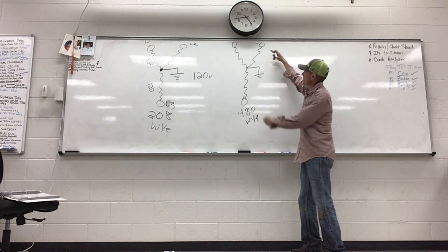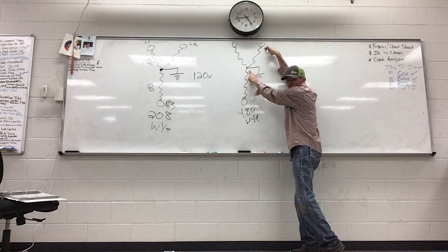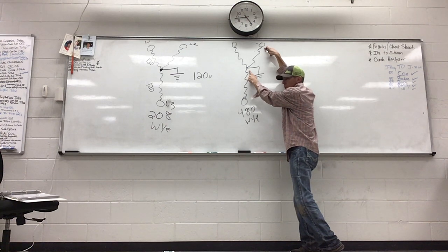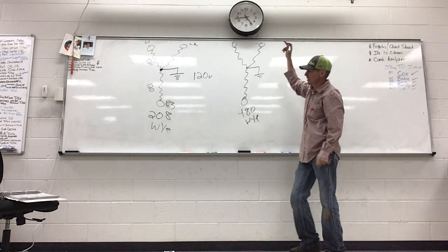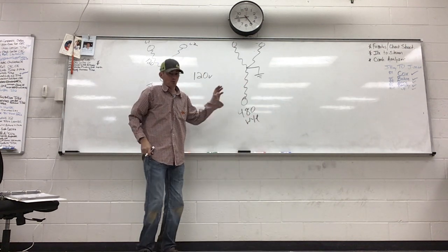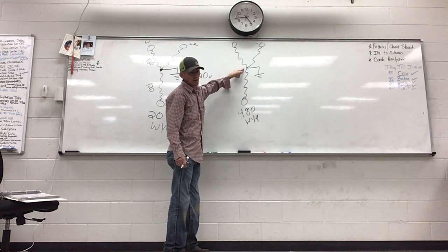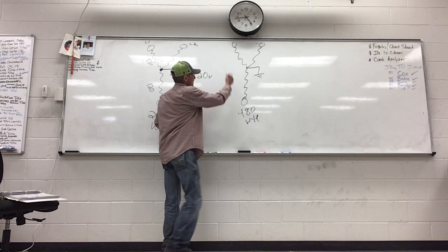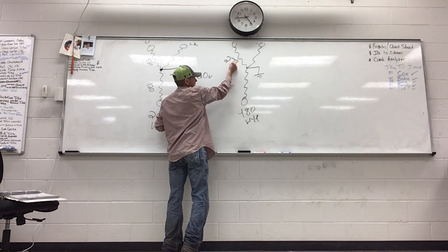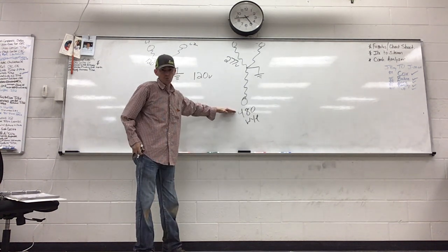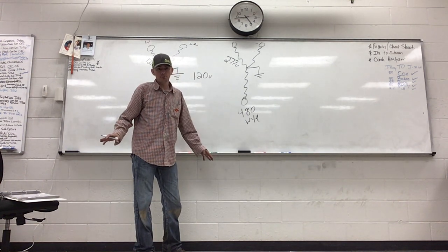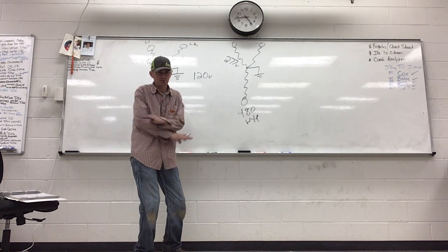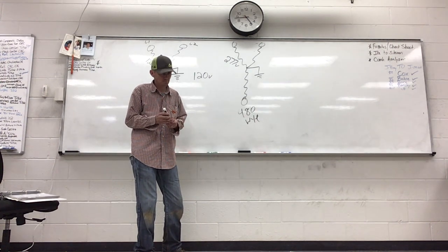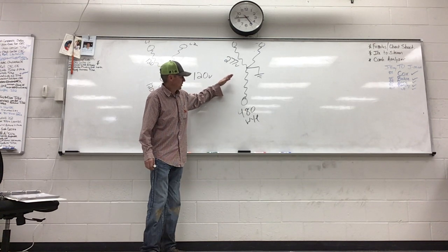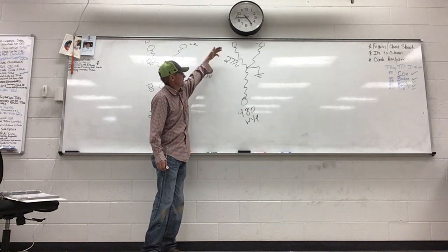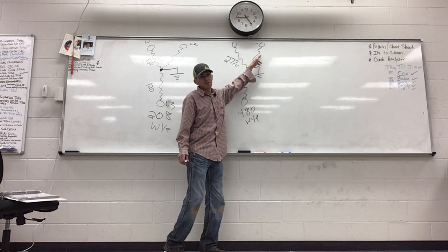Here's the kicker. If I go from leg to neutral ground, I do not get 120. As a matter of fact, if I go from any leg to ground, any leg to neutral, I'm going to get 277 volts. If it's a 480 volt building, there is no 120 volts feeding that building off the transformer. There's no 120 volts most of the time, okay? So on this 480 volt building, I get 480 leg to leg. I get 277 from any leg to ground.